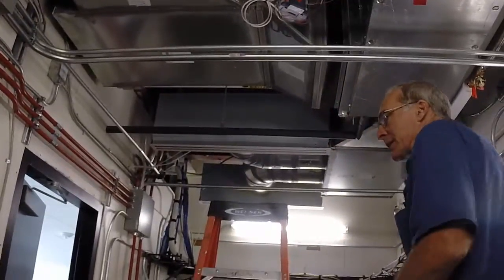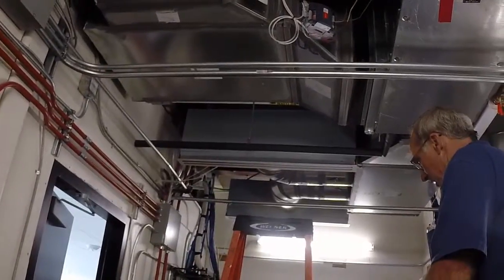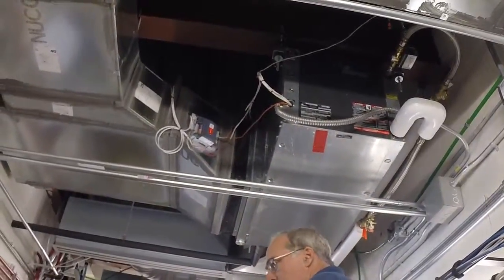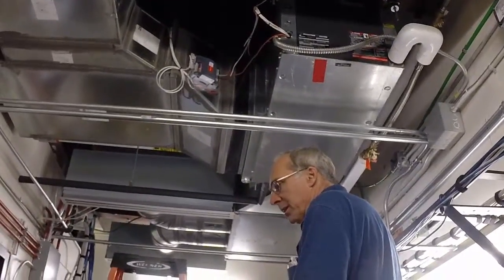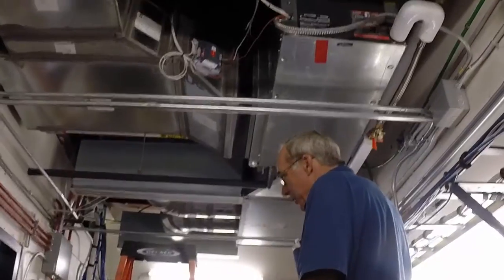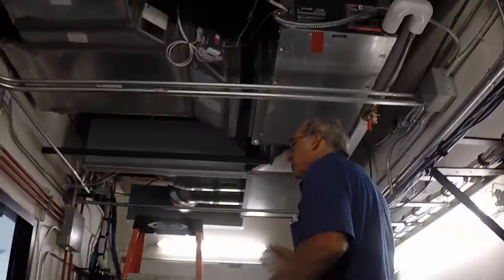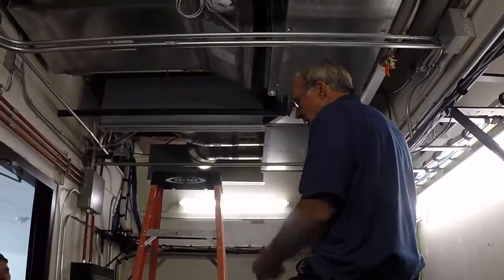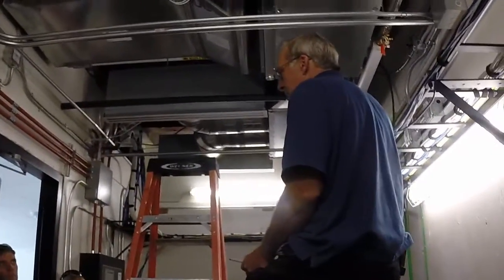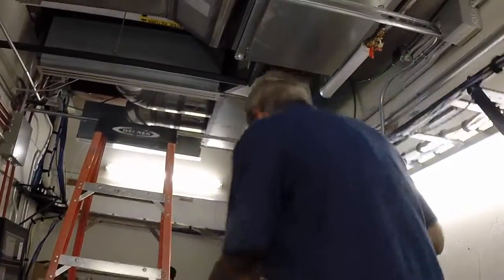See what happens a lot of times, if they had a winter with heat pump systems that don't have a big boiler, the temperatures start falling in the building loop. The temperature starts falling, and if you have 45, 40 degree water going through the system, and then you have a unit calling for cooling, it doesn't want to go into cool very well. The head pressure falls with it and you'll start tripping out on low pressure or alarms.